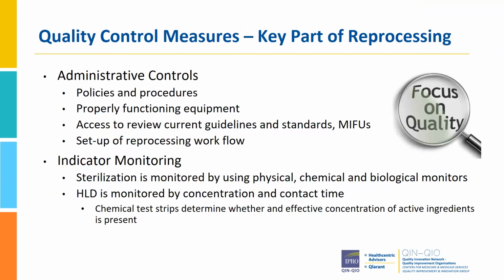Another part of reprocessing that's key is quality control measures. Every long-term care facility should have a system in place that allows for the provision of cleaning and disinfection and sterilization if that's something that you're doing. From an administrative perspective, there needs to be policies and procedures and properly functioning equipment, and access for staff to review current guidelines and standards and IFUs and keep up on that because it's ever changing.